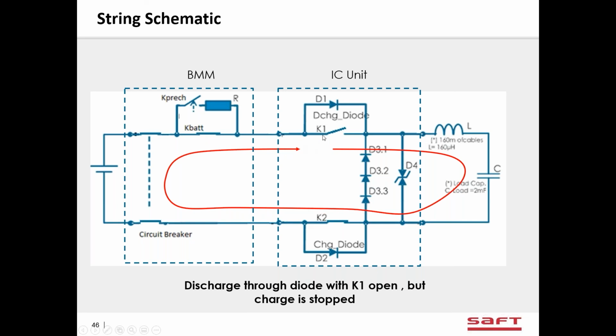So even though the contactor is open, we still can discharge to the load. So we open K1 to prevent overcharge. In this picture, imagine that one of the cells is at its maximum voltage and we don't want any more. We don't want to be overcharged. We open K1 so that no more charge current can get into the battery, and then of course it's blocked by the diode D1.